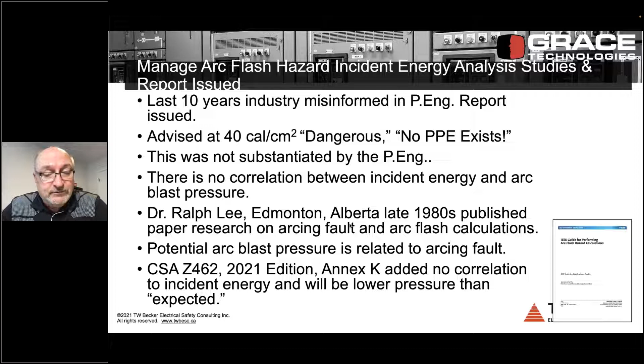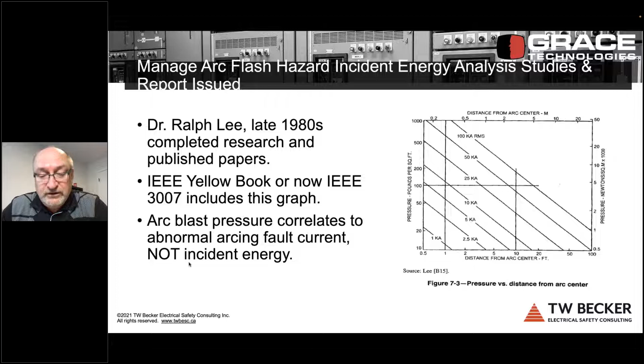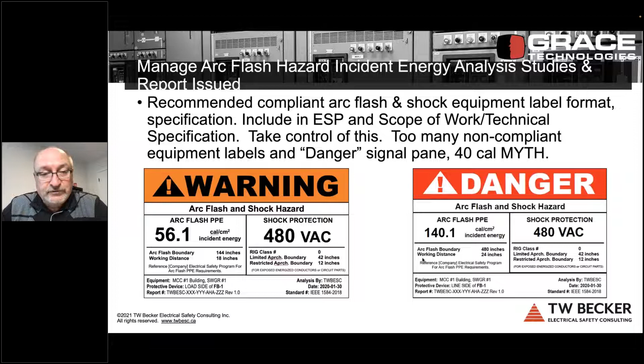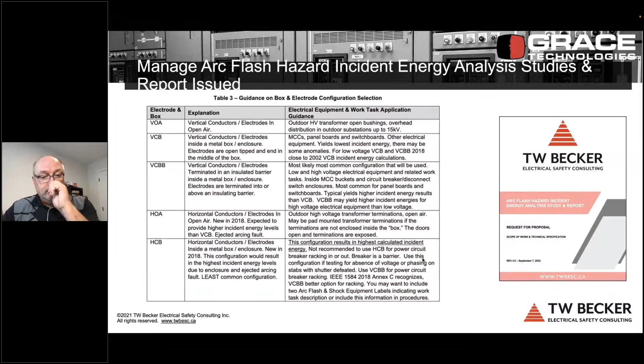So arc blast pressure doesn't correlate to incident energy. It correlates to abnormal arcing fault, which makes complete sense to me. This information is actually documented in the IEEE Yellow Book, or now the IEEE 3007 series documents. Arc blast pressure correlates to abnormal arcing fault, not incident energy. There is no 40 cal myth. Technically, the label danger should be at 140.1 calories because we don't have any arc flash PPE available with an ATPV greater than 140. There is a 140 cal arc flash suit available in the market, and it can be applied.